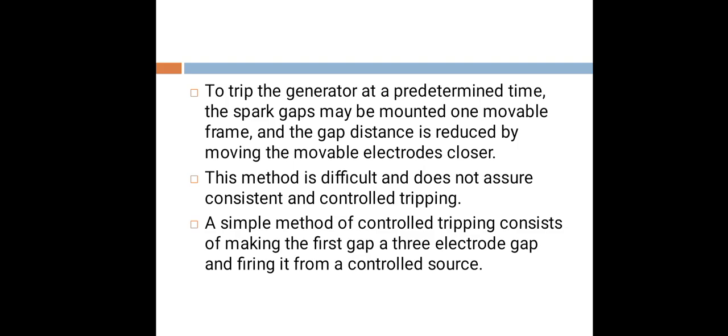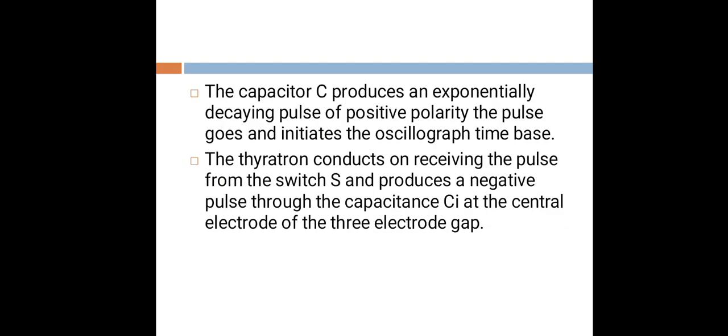A simple method of controlled tripping consists of making the first gap a three-electrode gap and firing it from a controlled source. The capacitor C produces an exponentially decaying pulse of positive polarity.